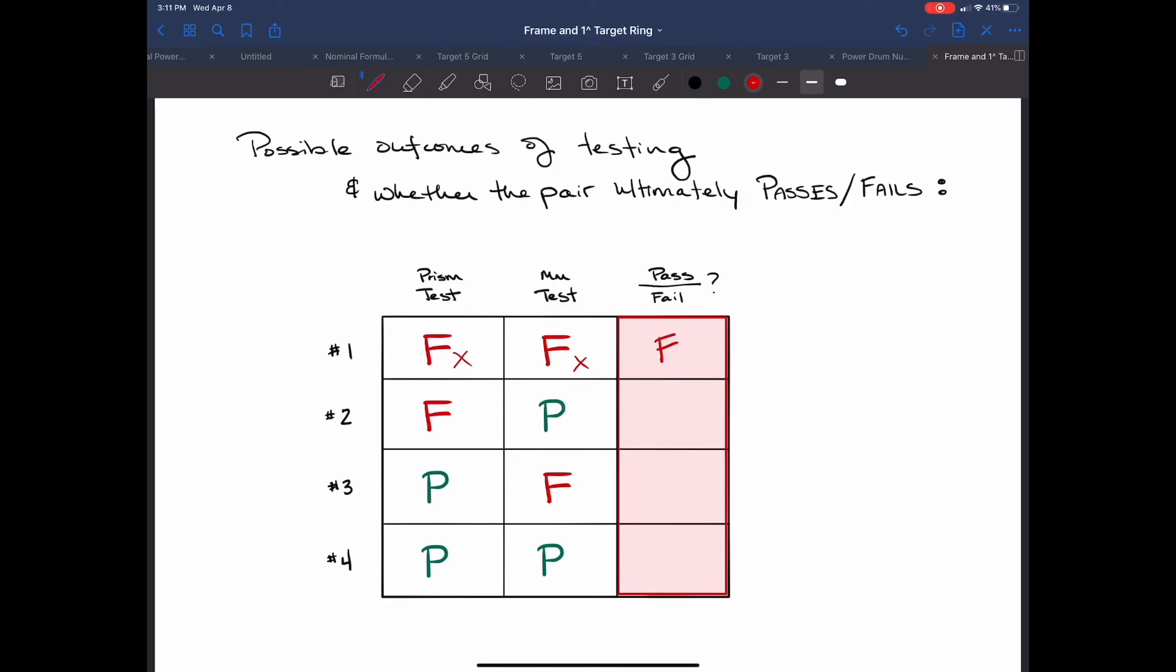If on another pair we failed the prism test but we passed the millimeter test then this pair would ultimately pass. If the prism test is passed but the millimeter test fails then this pair still will ultimately pass. If the pair passes the prism test and the millimeter test of course it passes. So the only time that the pair will fail is if both prism test and millimeter test fail.